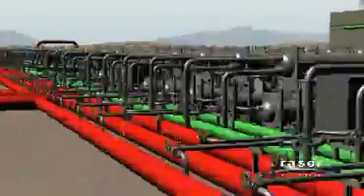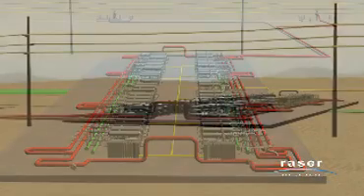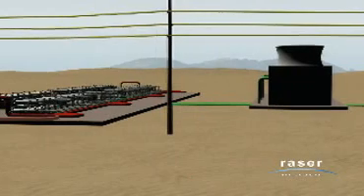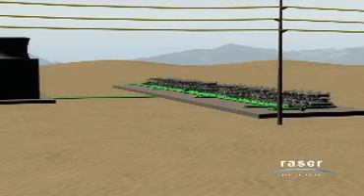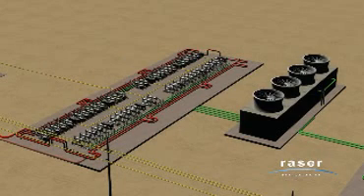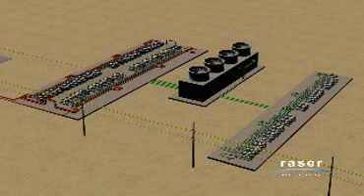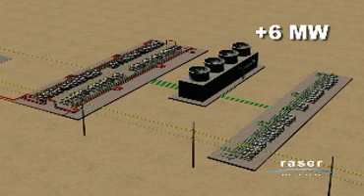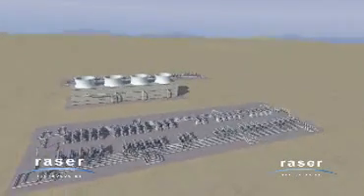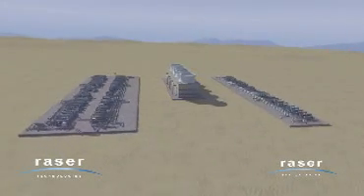Because Raser's binary power plant uses low temperature technology, even after generating 11 megawatts of power in the first phase, in many cases the well water is still hot enough to generate additional power. After leaving the first array of 50 units, the well water can be passed to a secondary power generation cycle, or bottom cycle. In the next phase of the plant, Raser will add a second array of 25 power generation units on the other side of the cooling towers, where an additional 6 megawatts of power can be generated. Cascading power generation in this way is highly productive and economical, because 50 percent more additional power can be generated without the expense of drilling additional wells.